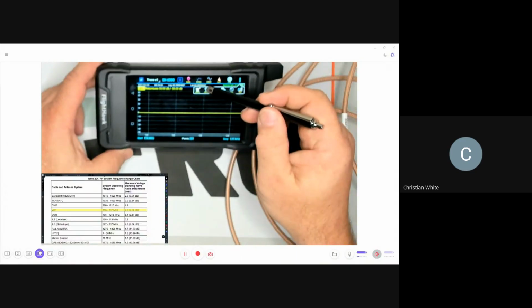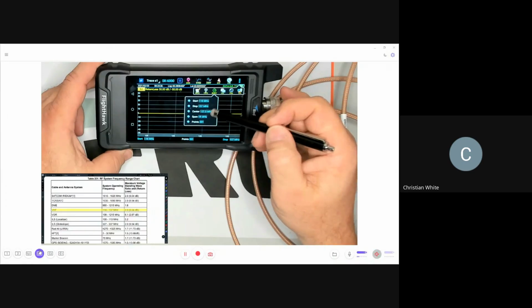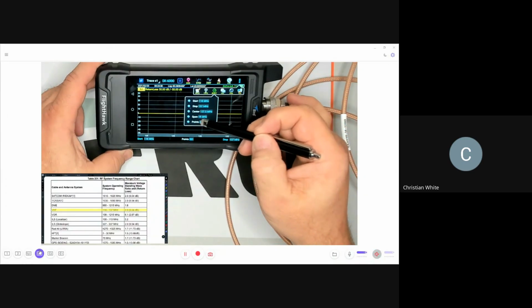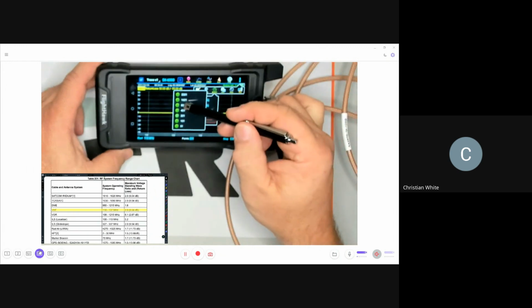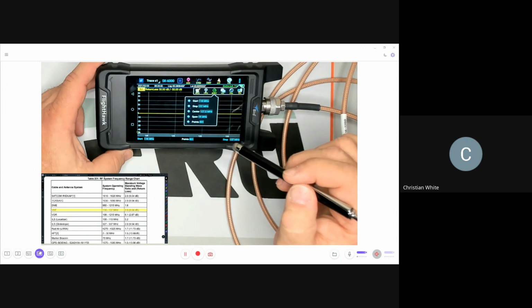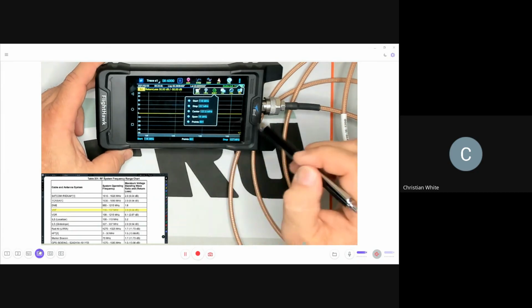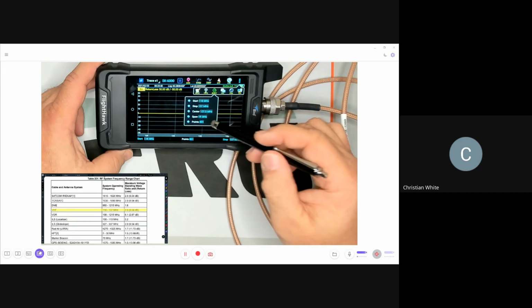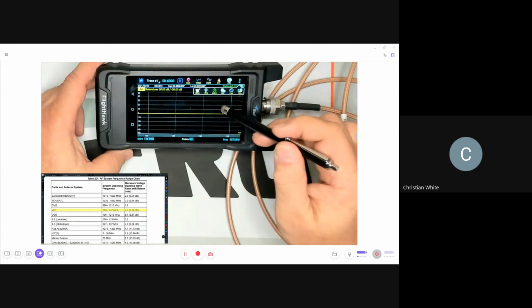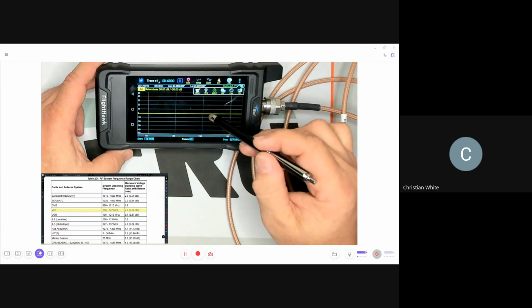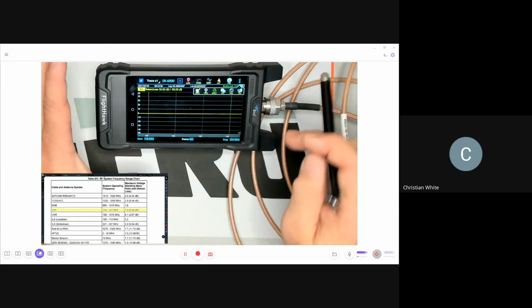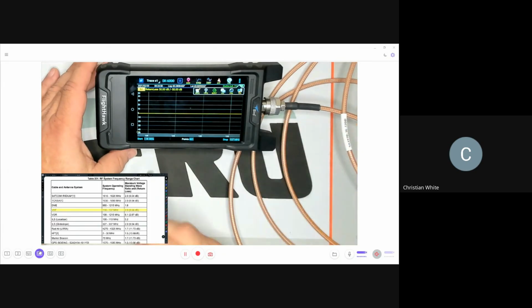And we also, in our frequency, I forgot to do it. We're not worried about the center. We're not worried about the span, but our points is really our resolution, how fine our points are going to be that it's going to plot out. So we usually go right in the middle. 801 is pretty much a standard for whatever we do. So we just set our frequency up for VHF, what this is going to scan. So this is going to send a frequency of 118 megahertz to 137 megahertz. It's going to scan that whole frequency through this whole coax cable and our antenna, whatever that we're doing.